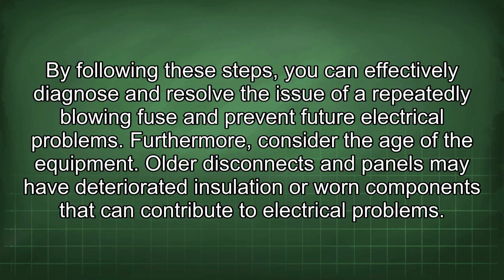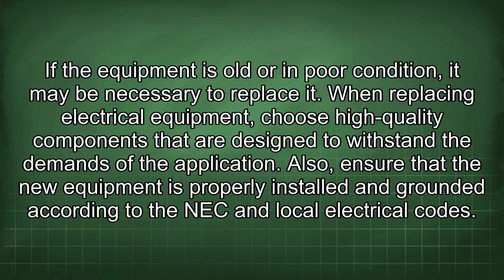Older disconnects and panels may have deteriorated insulation or worn components that can contribute to electrical problems. If the equipment is old or in poor condition, it may be necessary to replace it. When replacing electrical equipment, choose high-quality components that are designed to withstand the demands of the application. Also, ensure that the new equipment is properly installed and grounded according to the NEC and local electrical codes.